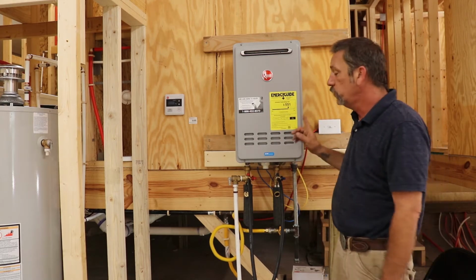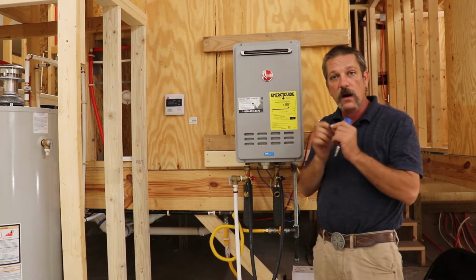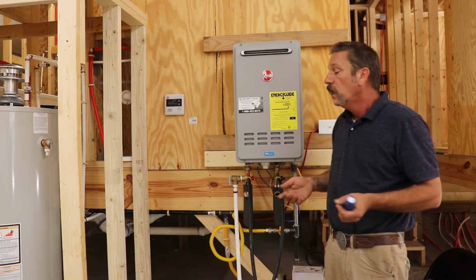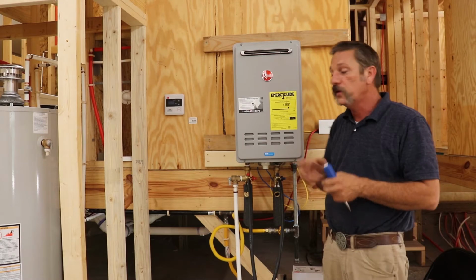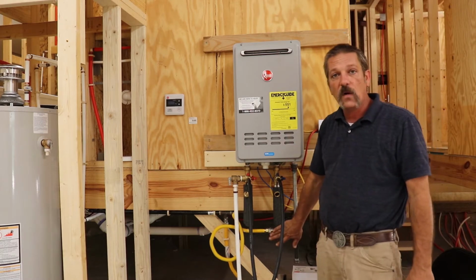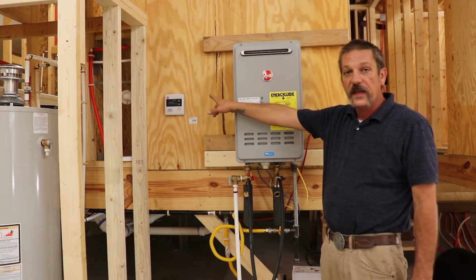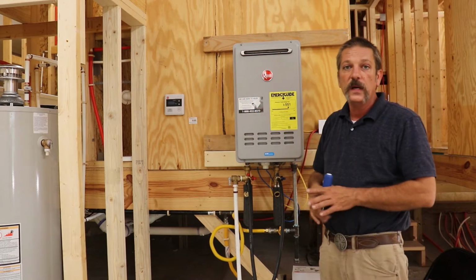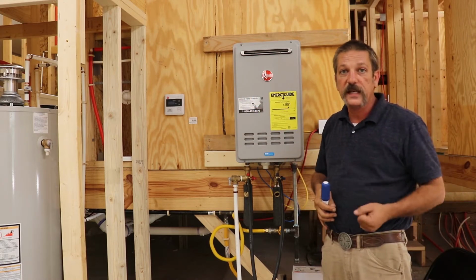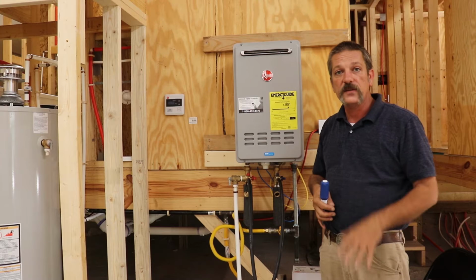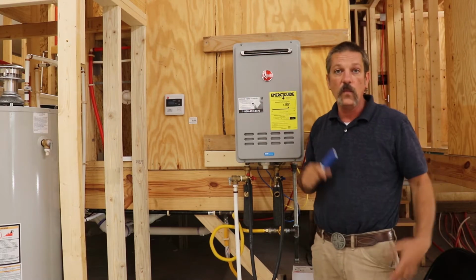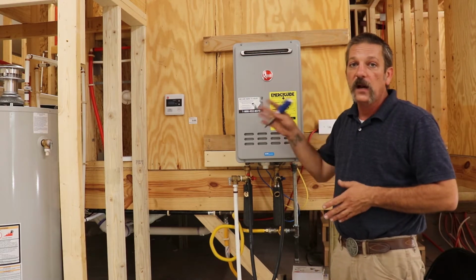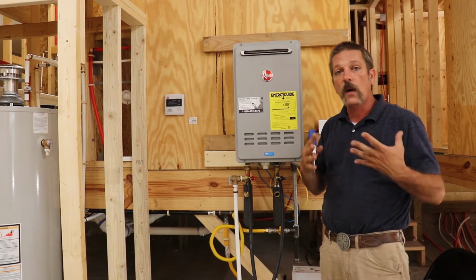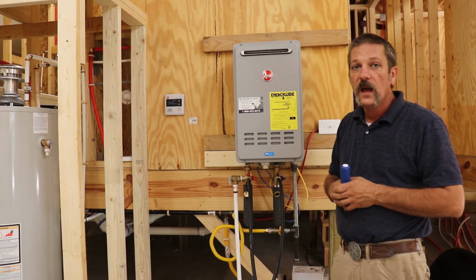Now, if you're using a water heater that's got that wire and harness with the flush function, you're going to snap that together, leave the power and gas on, and let that controller count down. It's going to start at 60, count down as you go, and it will beep at you to tell you when your time's up. It's pretty neat, and it'll also keep a record that the water heater has been flushed out.